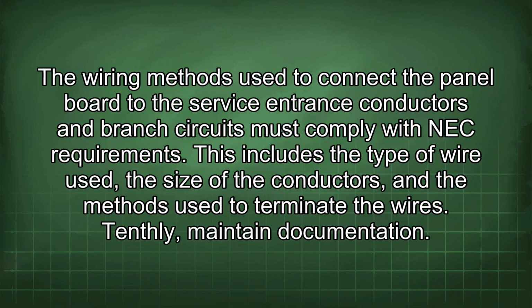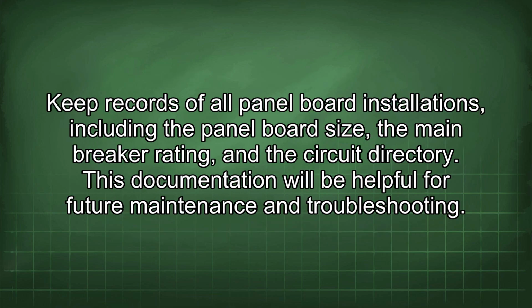The wiring methods used to connect the panel board to the service entrance conductors and branch circuits must comply with NEC requirements. This includes the type of wire used, the size of the conductors, and the methods used to terminate the wires. Tenthly, maintain documentation. Keep records of all panel board installations, including the panel board size, the main breaker rating, and the circuit directory. This documentation will be helpful for future maintenance and troubleshooting.